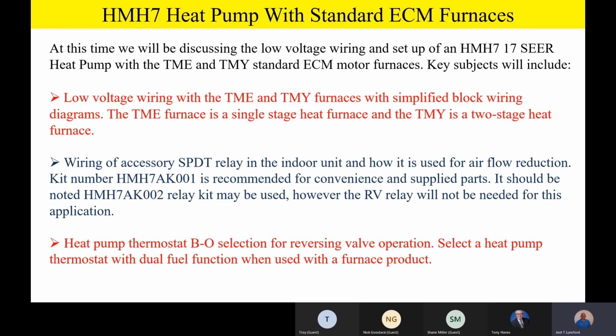Now remember, on the heat pump thermostat, you have to have that BO selection for reversing valve operation. In addition, if you're going to be doing a dual fuel, in other words, you're going to be marrying this heat pump to a furnace, you're going to have to select a heat pump thermostat with dual fuel function whenever you use it with a furnace product. So that's not a big deal. Just please remember that your heat pump thermostat has to be a dual fuel thermostat with a furnace, and it has to have that BO selection so we can energize that B terminal in the heating mode of operation on the heat pump.